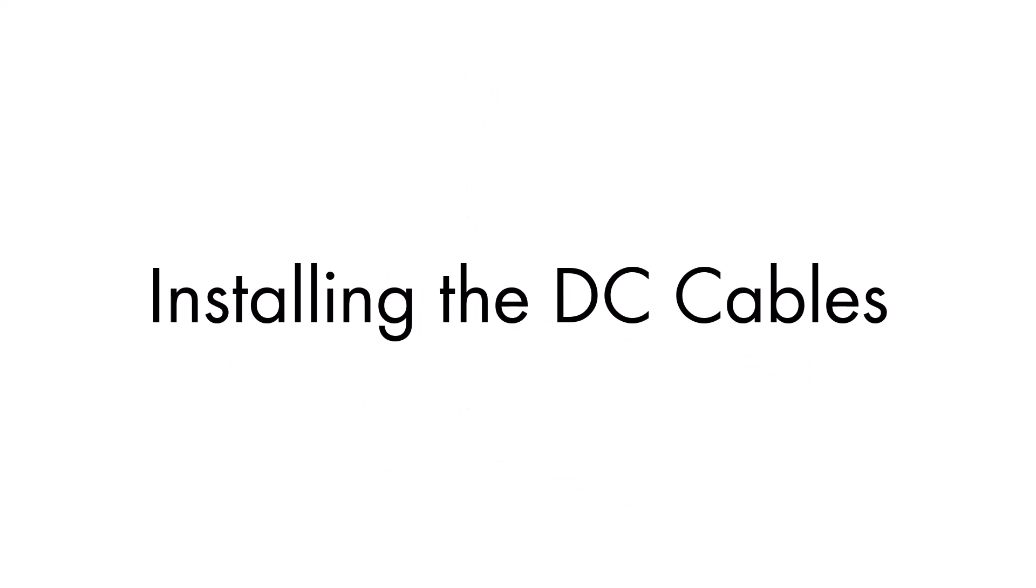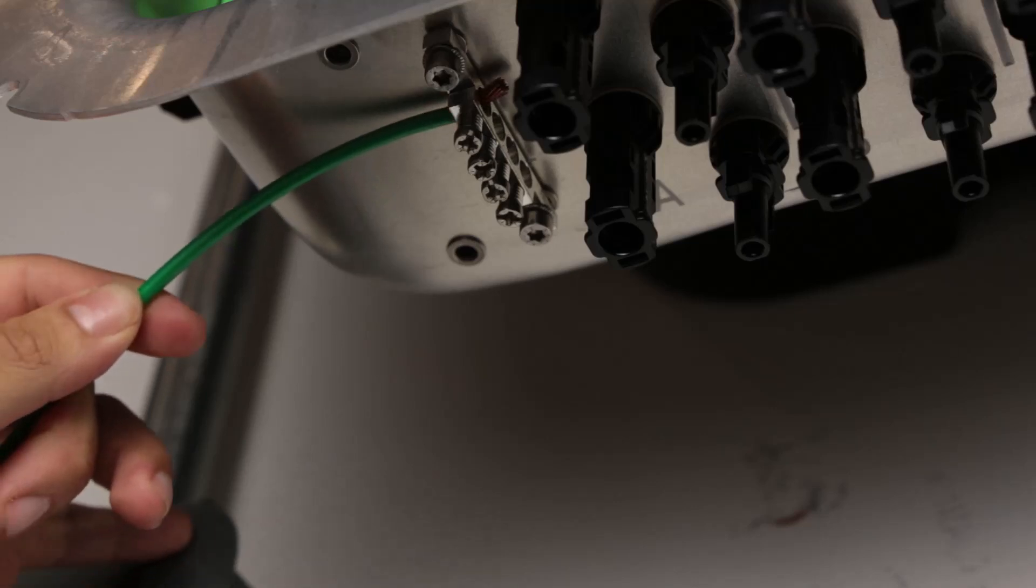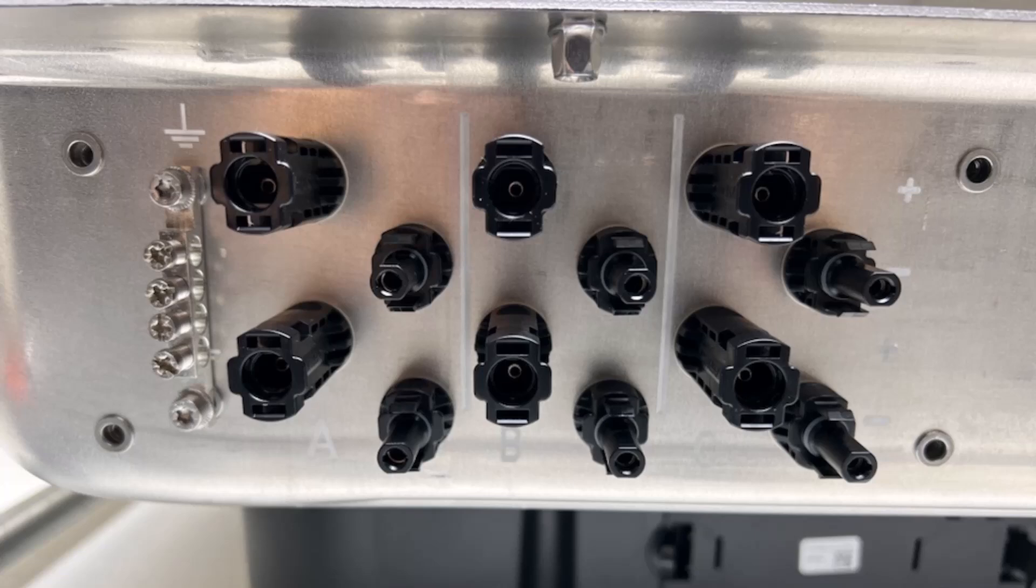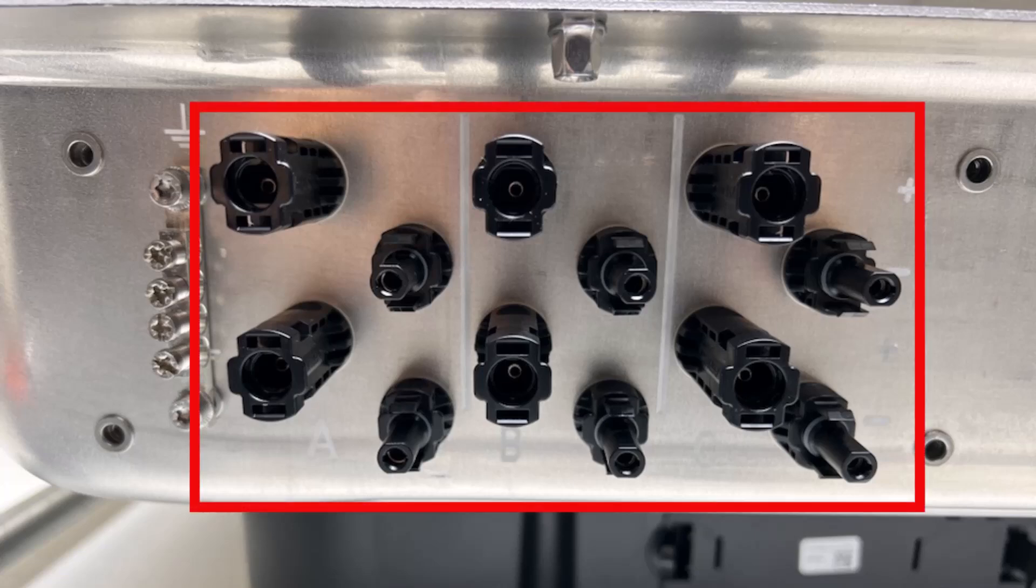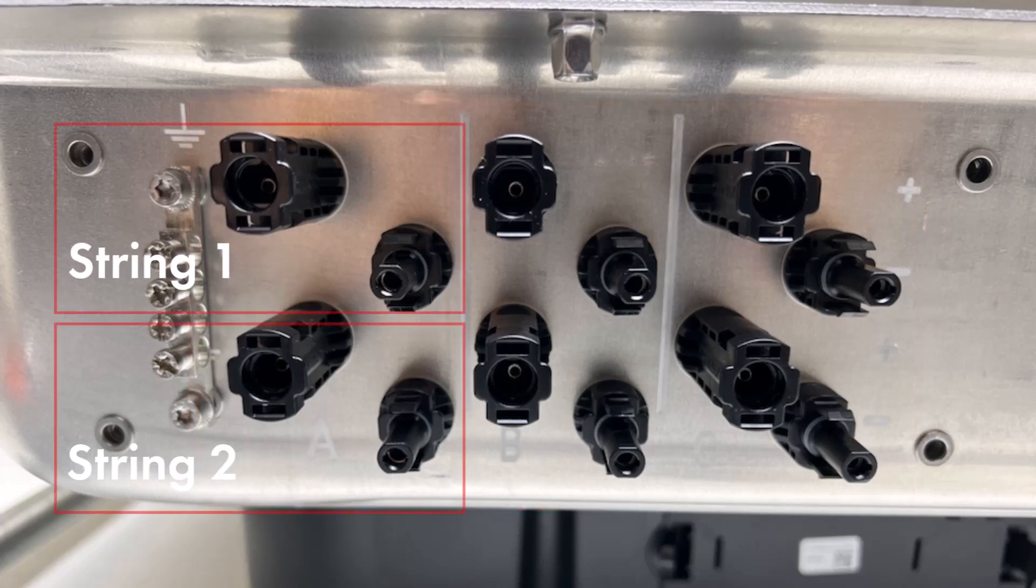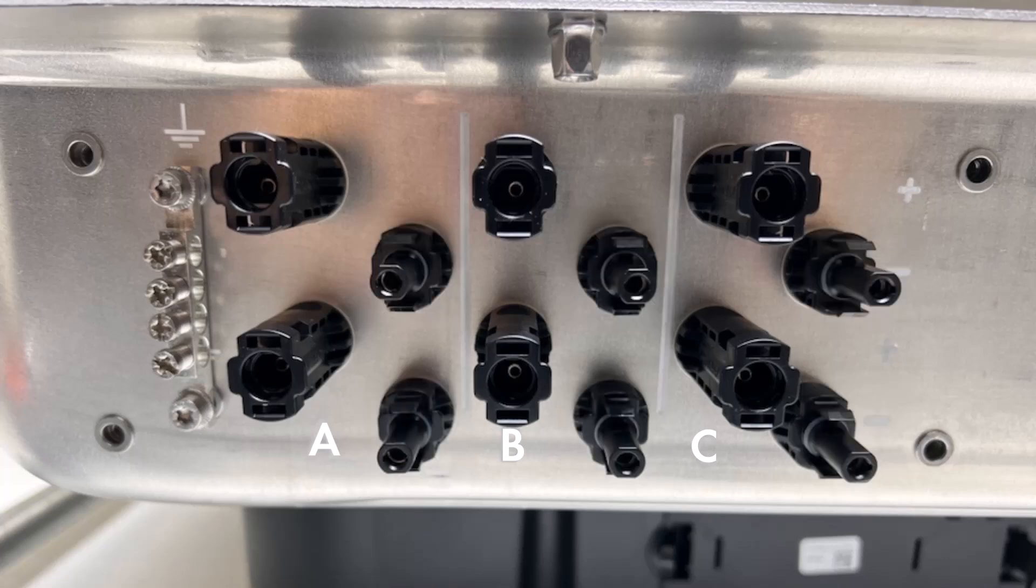Now it's time to connect the home run cables to the inverter bulkhead terminals. Start by connecting the equipment grounding conductor to the ground bus bar. Notice the connector locations here. You have three MPPT channel inputs with two string connections for each, labeled A, B, and C. The connectors to the left are positive, while the connectors to the right are negative.